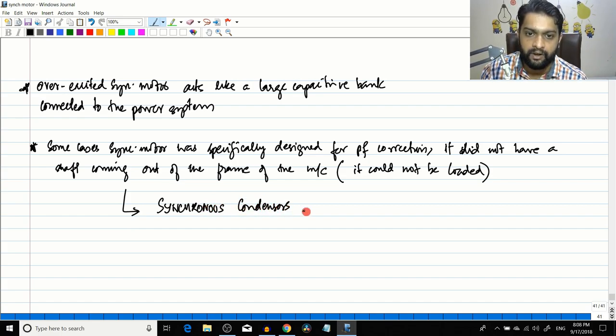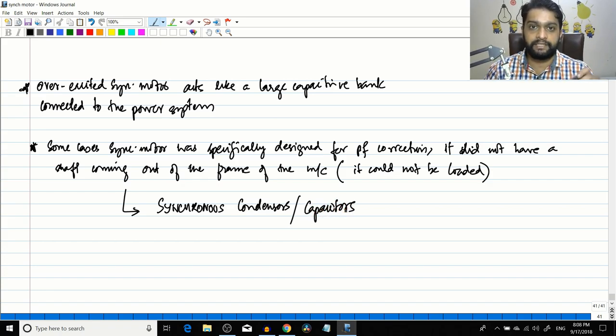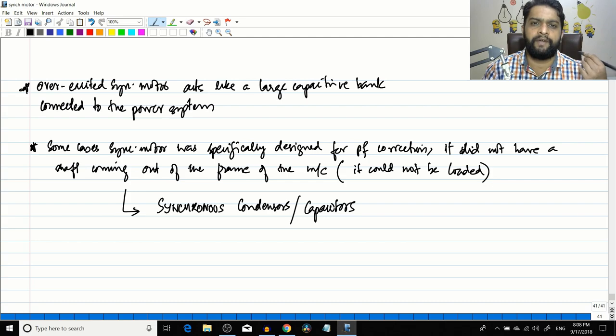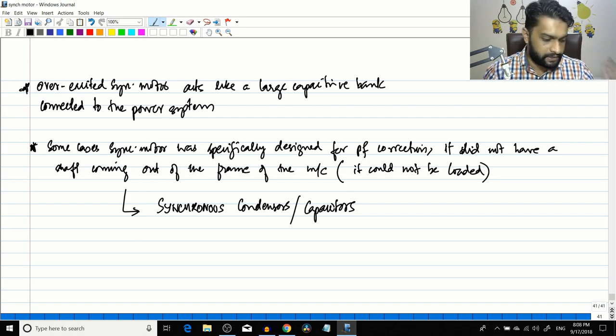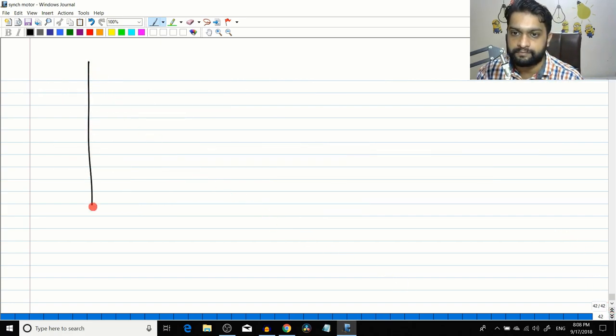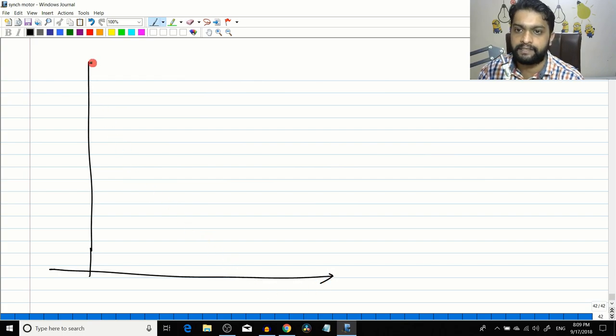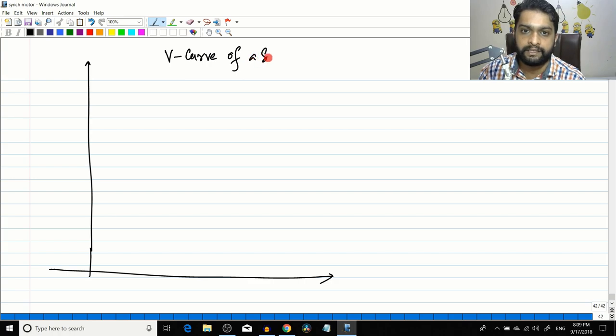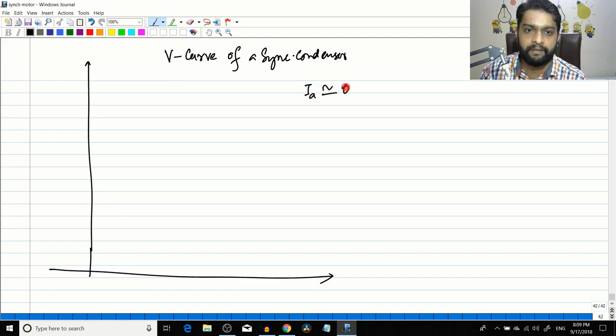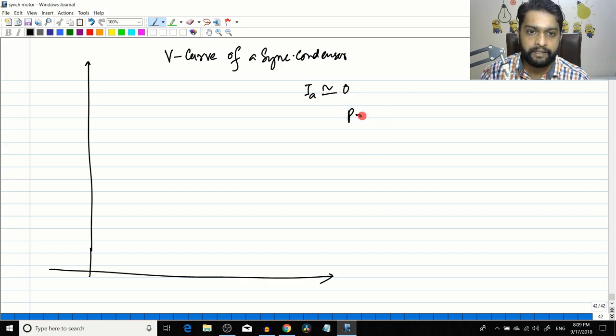Synchronous condensers or synchronous capacitors are basically synchronous machines specifically designed for power factor correction. They run at no-load condition because in the no-load condition they have a very similar property to that of a capacitive bank connected to the power system. So what will be the V-curve of such a system? For a V-curve for a synchronous condenser - I hope you remember what a V-curve is - here Ia is approximately equal to zero.